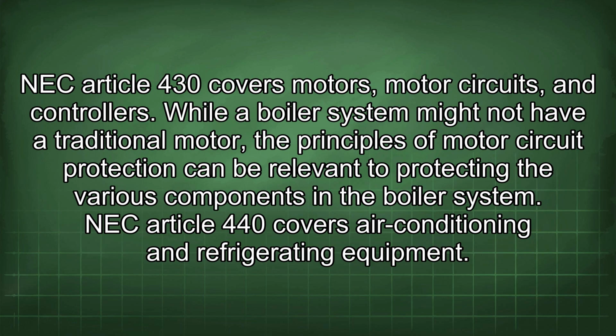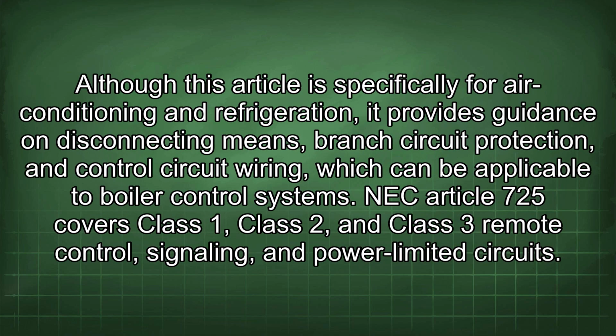NEC Article 430 covers motors, motor circuits, and controllers. While a boiler system might not have a traditional motor, the principles of motor circuit protection can be relevant to protecting the various components in the boiler system. NEC Article 440 covers air conditioning and refrigerating equipment. Although this article is specifically for air conditioning and refrigeration, it provides guidance on disconnecting means, branch circuit protection, and control circuit wiring, which can be applicable to boiler control systems.